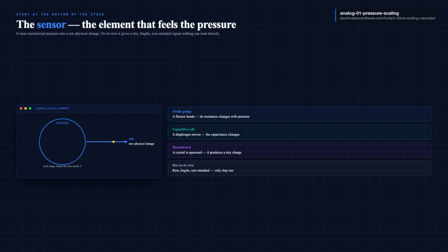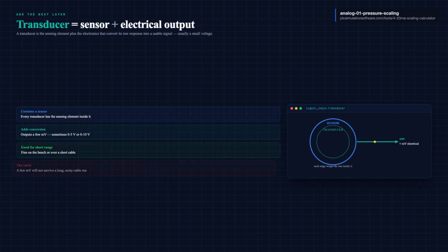Now add the next layer. A transducer. A pressure transducer is the sensing element, plus the electronics that convert its raw response into a usable electrical signal. Usually that is a small voltage, a few millivolts, sometimes a 0 to 5 volt or 0 to 10 volt output. So every transducer contains a sensor, but it adds the conversion step. That is the whole idea. Sensor plus a low-level electrical output equals transducer. And for a lot of bench and short-range uses, that is enough. The problem shows up over distance. A few millivolts will not survive a long cable run through a plant full of motors and drives. The noise eats it, which is exactly why the third device exists.